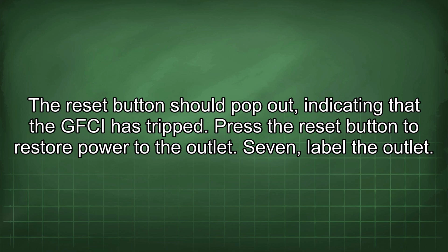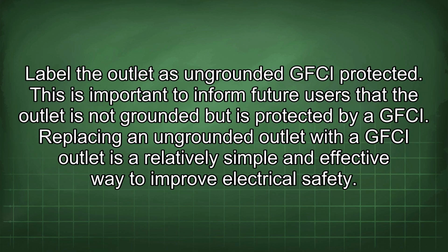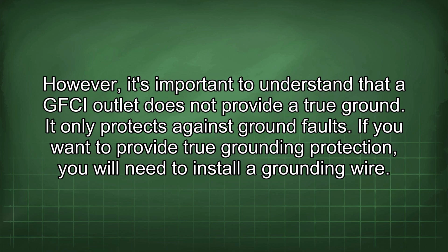7. Label the outlet. Label the outlet as ungrounded GFCI protected. This is important to inform future users that the outlet is not grounded but is protected by a GFCI. Replacing an ungrounded outlet with a GFCI outlet is a relatively simple and effective way to improve electrical safety. However, it's important to understand that a GFCI outlet does not provide a true ground. It only protects against ground faults. If you want to provide true grounding protection, you will need to install a grounding wire.